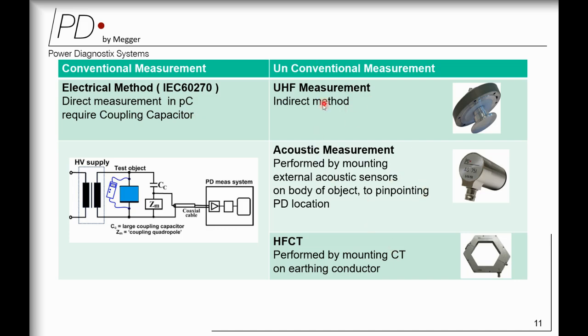So there are different techniques: the UHF technique for the GIS, acoustic for pinpointing, and third, HFCT. When you talk about the GIS, a few people say we only do acoustic measurement. But the problem with acoustic is that it is a second step of measurement. It is not the initial action to be taken on the asset. UHF always helps you understand in which segment you have a partial discharge, and then to pinpoint it, you can use acoustic measurements.